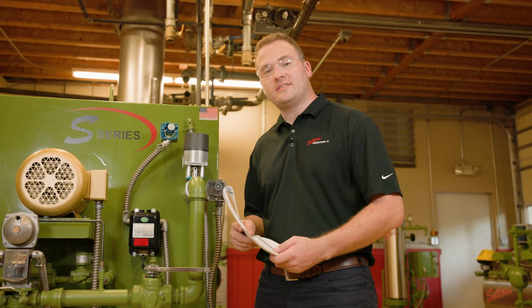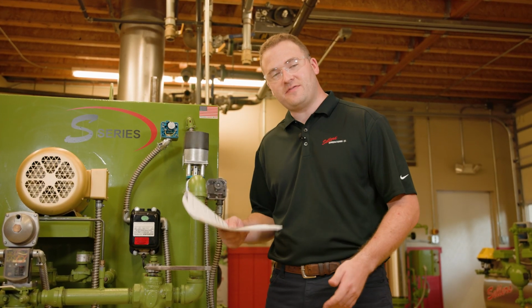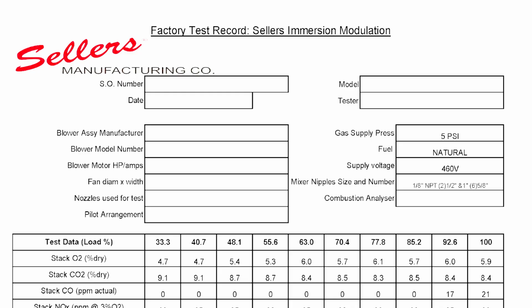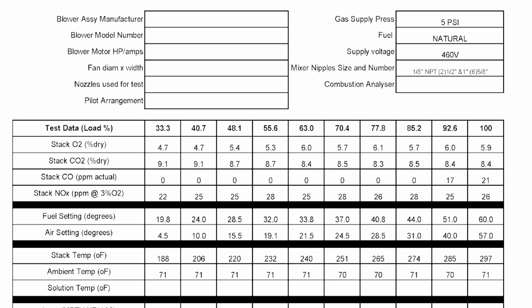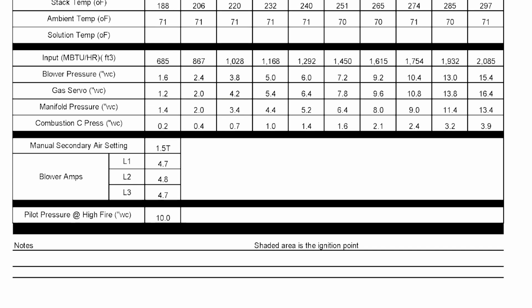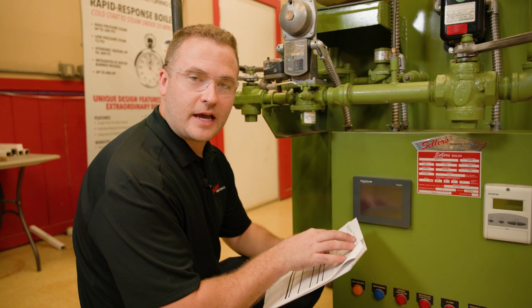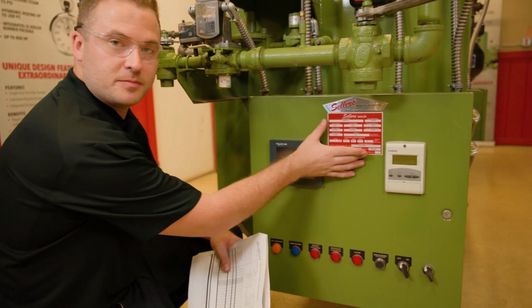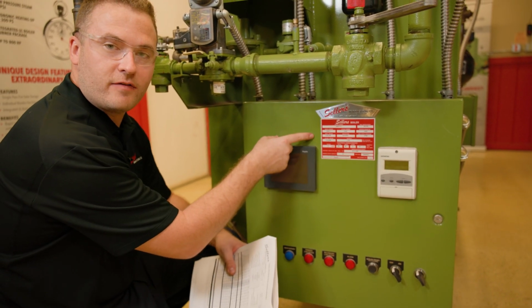Did you know that every single Sellers Manufacturing boiler is test fired before it leaves the factory? Yes, every single boiler. And when they test fire it, they make a report that shows the numbers and the factory setup. To make sure you have the correct test report, the numbers on the test report are going to match the Sellers Manufacturing sticker on the front of the electrical panel.